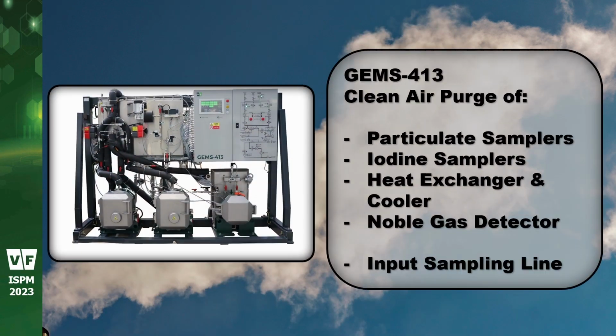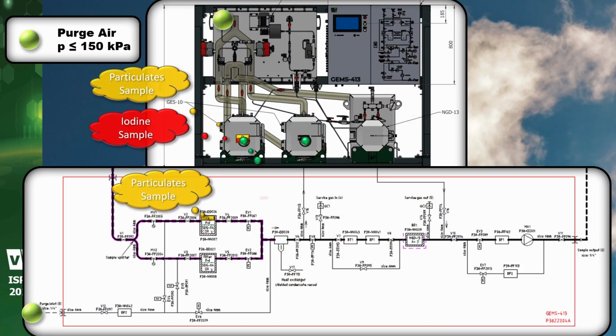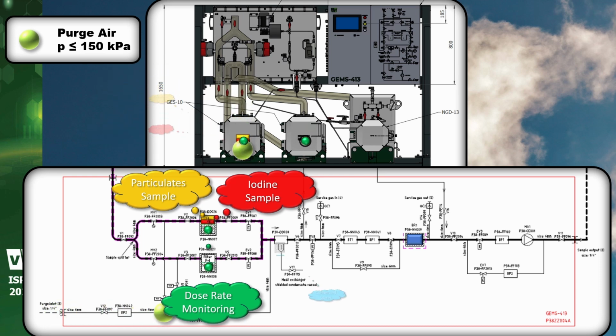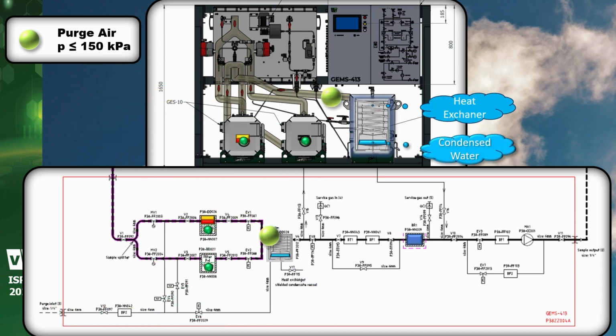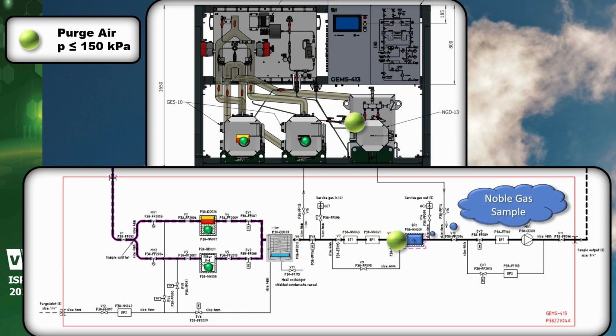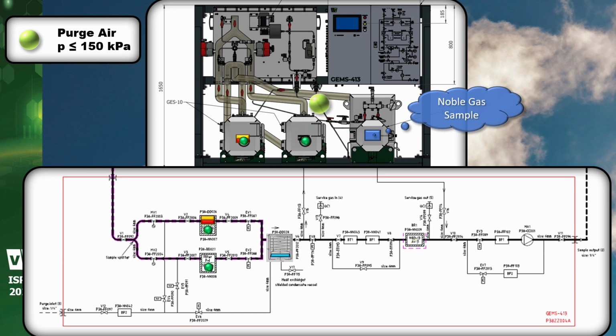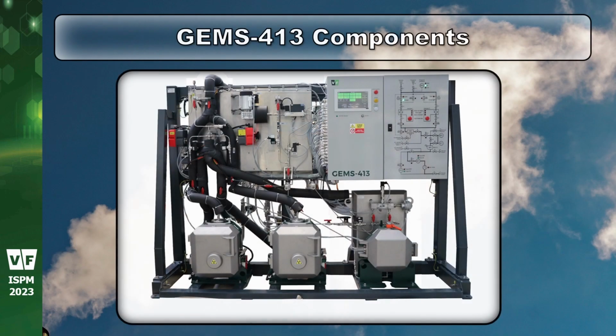The GEMS-413 allows purging of particulate and iodine samplers, noble gas detector and the input part of the sampling line from the ventilation stack with pressurized clean purge air. The pressurized clean purge air with maximum pressure 150 kilopascals is brought to the purge air inlet. Maximum purge air pressure is checked and air with higher pressure is not allowed into the monitor. The purge air is returned to the ventilation stack. The GEMS-413 main components description follows.